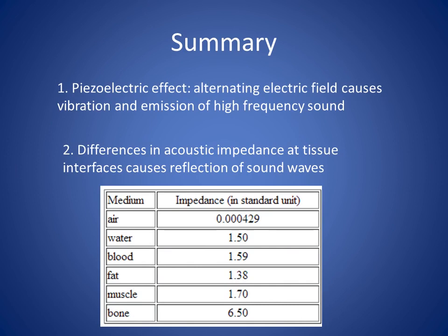Different body layers, such as fat, muscle, and many body organs, have very similar acoustic impedances, so that most of the beam will pass from one layer into the next, and only a small fraction is reflected. In practice, this is not a problem. In fact, the imaging technique relies on it. To obtain a reasonable image, with good resolution of an interface between two layers, around 1% of a beam should be reflected, leaving a substantial portion to continue on to further reflections.